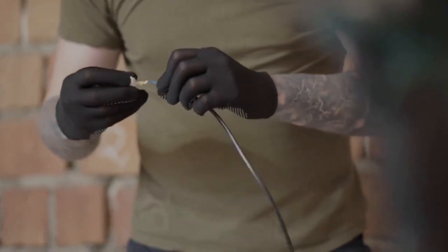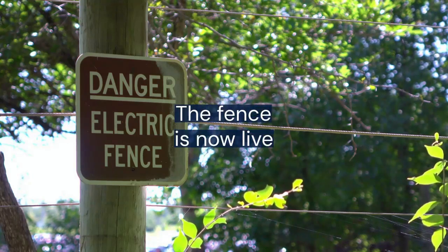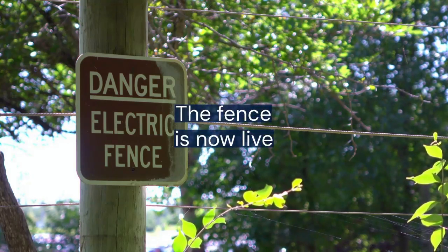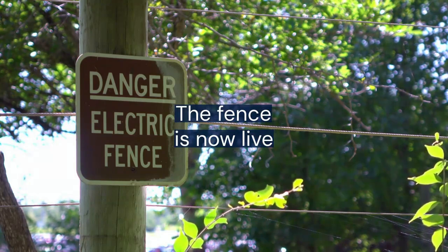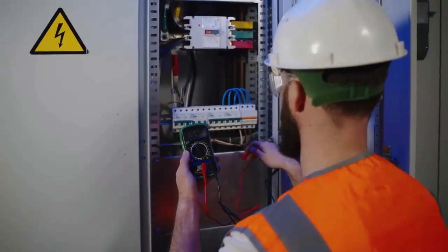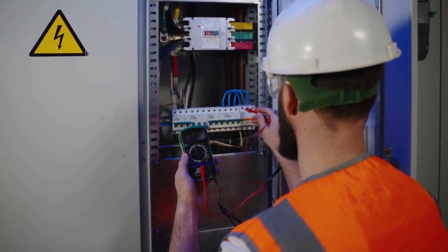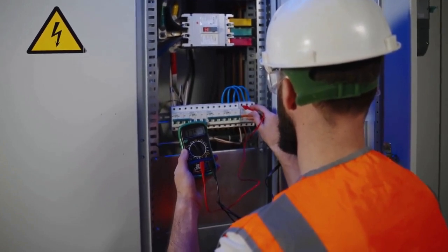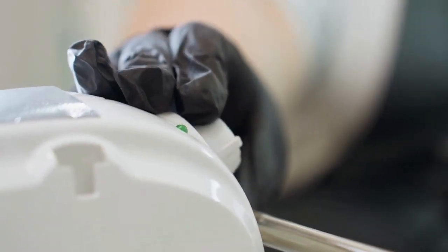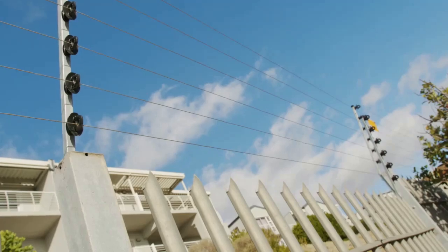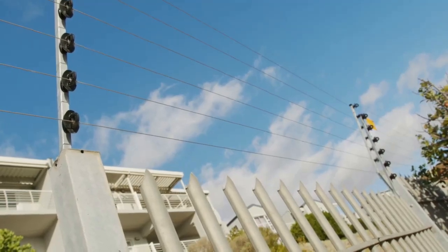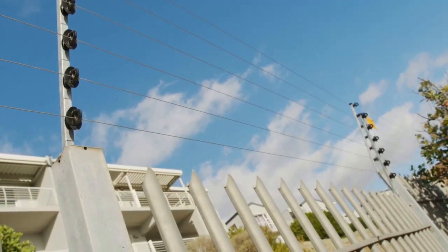With your multimeter set up and your safety gloves on, you can now turn your fence energizer back on. Be extremely cautious as the fence is now live. Carefully take the red probe of your multimeter and firmly touch it to the main electric fence wire. Then take the black probe and touch it to a good ground source. This could be the dedicated ground rod for your fence, or another reliable earth connection.